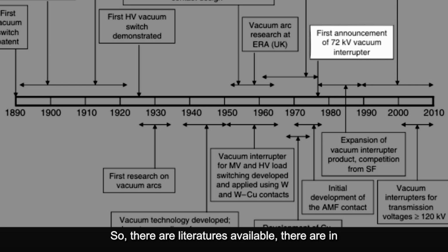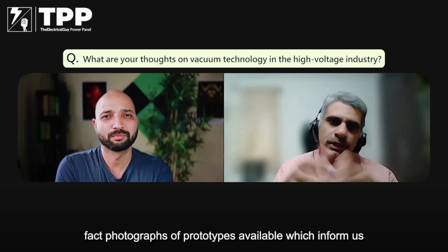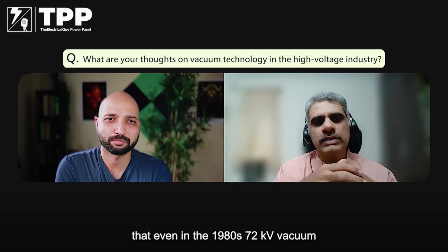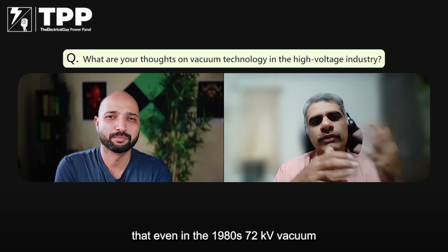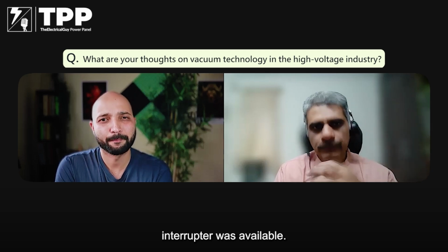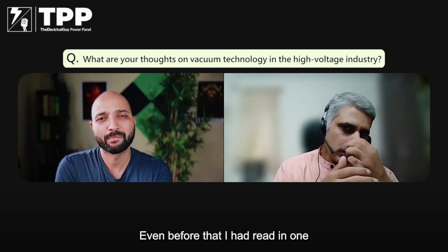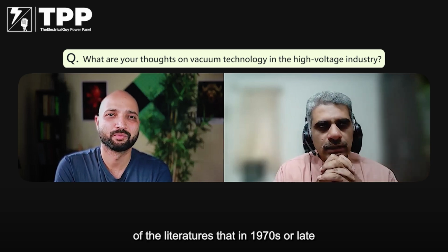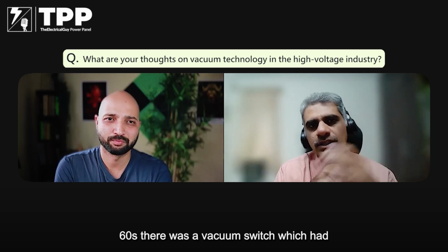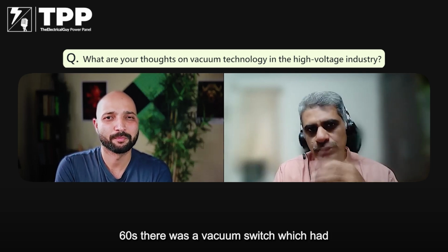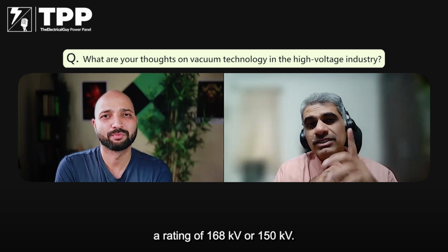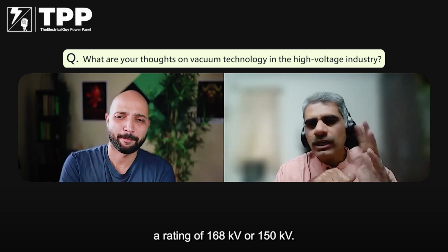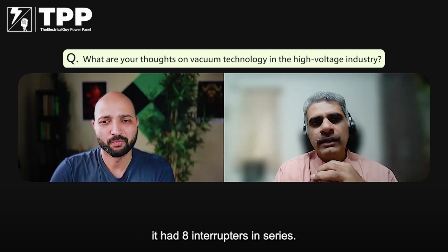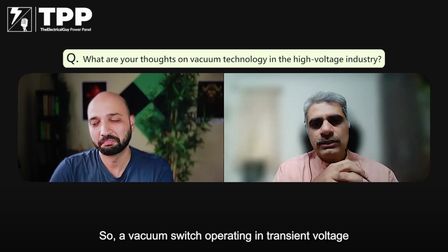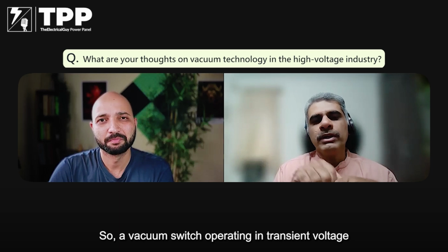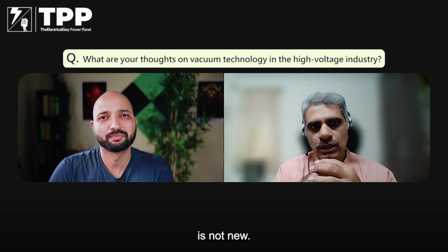So there are literatures available. There are, in fact, photographs of prototypes available, which inform us that even in the 1980s, a 72 kV vacuum interrupter was available. Even before that, I had read in one of the literatures that in the 1970s or late 60s, there was a vacuum switch which had a rating of 168 kV or 150 kV. I don't remember the exact rating, and it had 8 interrupters in series. So a vacuum switch operating at transmission voltage is not new.